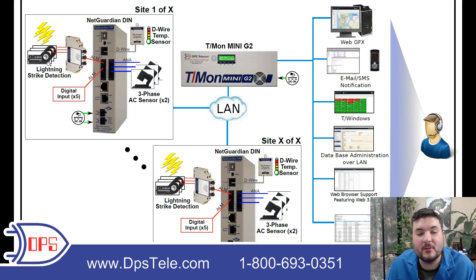The issue we initially ran into was that because this is a solid core, you have to pass your grounding through it, and that grounding shouldn't be cut. A client actually found something at a trade show — some hardware that clamps around your grounding system and routes around it as a little auxiliary flow of electricity, which you can then pass through the solid core. If you have any questions about specifically what that is, just give us a call.